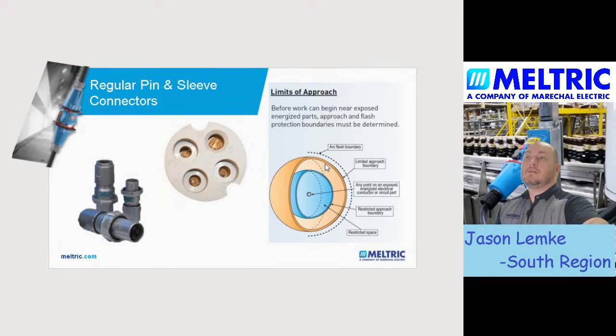So one of the really neat features about a Meltric device is that when you remove the plug, we have a dead front shutter that closes off all of the live conductors from anybody accessing them. So when it's in an enclosed space, we have no exposed electrical conductors, and therefore we have no restricted approach boundary, limited approach boundary, however you want to say it.